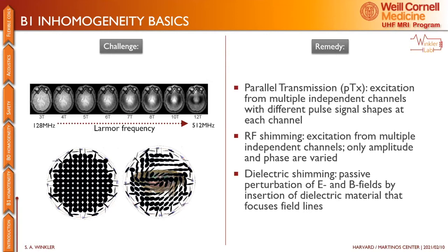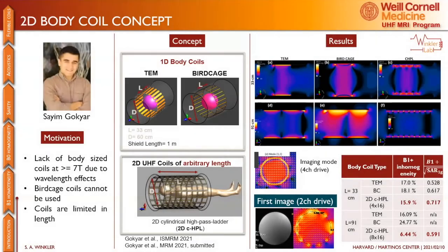So you don't just excite from two channels as in the quadrature case that's used at lower field strengths, but you actually have more channels and you have different pulse signal shapes even per channel. RF shimming is a simplified form of that. It does the same thing, but instead of changing the signal shapes, it only varies the amplitude and phase. And then one other fun thing here is dielectric shimming. It's actually gaining a lot of popularity. I worked on it long ago, but since then, a lot of people have been picking up this work and doing more in it. So it's exciting to see. What you can do here is passively perturb electric and magnetic field lines by inserting materials with high permittivity into the bore near the anatomy. All right, so that brings me to the first research topic in this area. This is very, very recent.